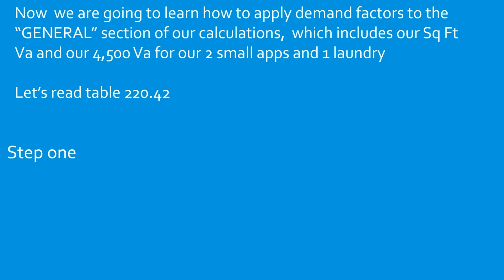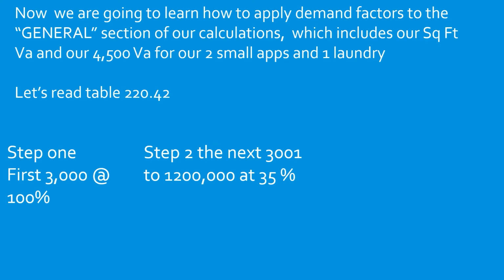Step 1 says the first 3,000 VAs, you're going to take at 100%, and I'm going to teach you how to set those to the side. Step 2 says we take the next 3,001 up to 120,000 and multiply that by 35%. If there's anything over 120,000, we would take that portion at 25%. But most often, with a single-family dwelling or even a small multifamily dwelling unit, you're not going to get that high in the VAs. But we do have some of that in our program.